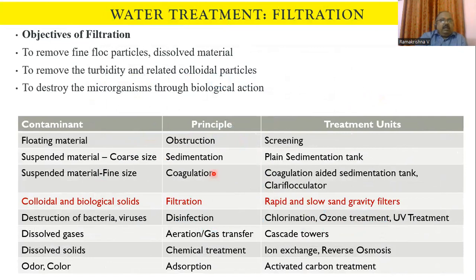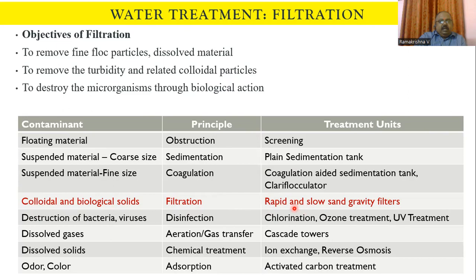Looking at the objectives of filtration in water treatment: filtration removes fine particles and floc particles, dissolved material, turbidity, and related colloidal particles — which are less than one micron in size. Filtration also removes some microorganisms through biological action. Removal of colloidal and biological solids is the major principle.